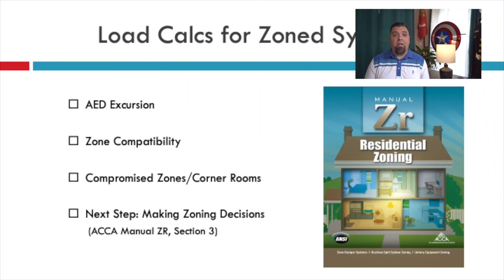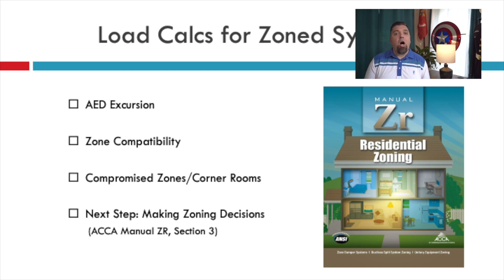Just to recap: we talked about AED excursion and how to know when you need to zone a system. We talked about zone compatibility — remember, it's not just the biggest rooms or ones that face south. They need to be compatible directionally, by time of day, or by floor. We covered compromised zones and corner rooms and how to handle those. If you're not sure about zoning and don't know what to do next, take a look at the video on Section 3 of ACCA Manual ZR called 'Making Zoning Decisions' — highly recommended before zoning out your next house.